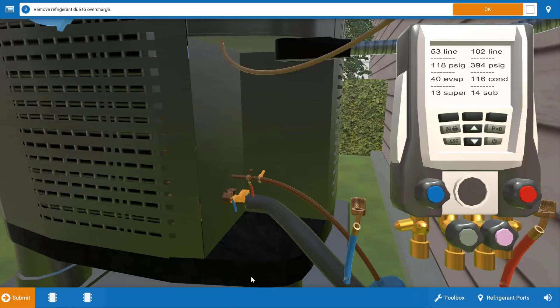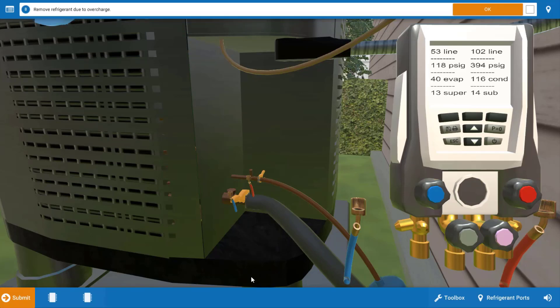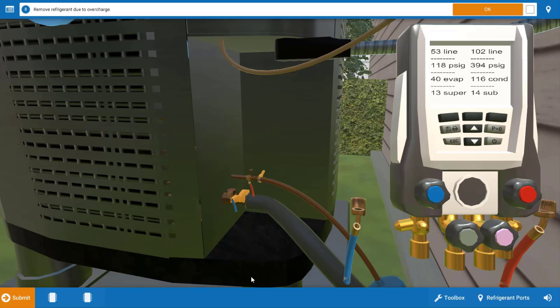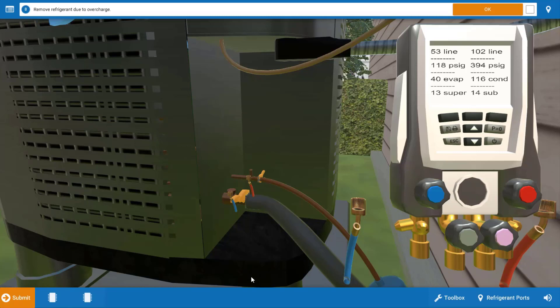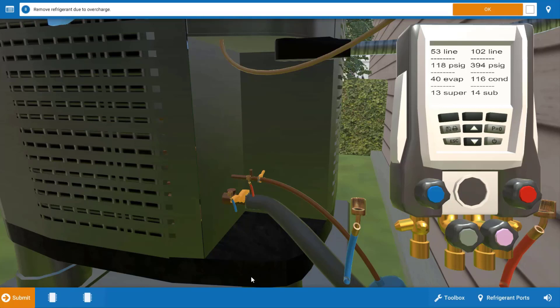In removing refrigerant the proper way to do this is to use a recovery cylinder and hook it up to the middle hose on the gauge manifold in this case where the pink knob is. To remove refrigerant you're going to need to open up the red valve because the pressure in the high side on the liquid line is going to be greater than the tank pressure. When we're adding refrigerant we have to add it through the suction which is the blue knob, but in this case we're removing it and the pressure is going to be higher there. So when we open up that red knob and that pink knob that refrigerant comes out and goes into the tank and you're going to want to do this incrementally because it can happen real quick and it can result in you taking too much refrigerant out of the system.